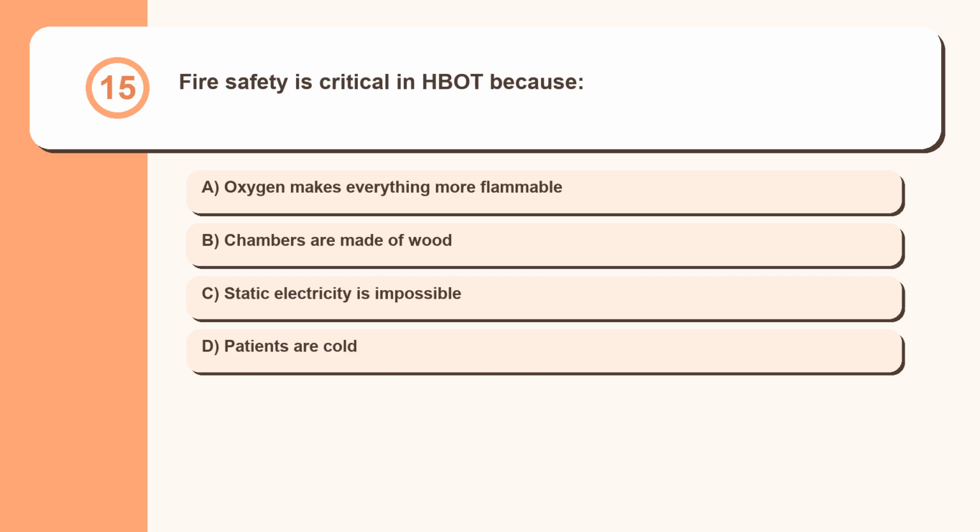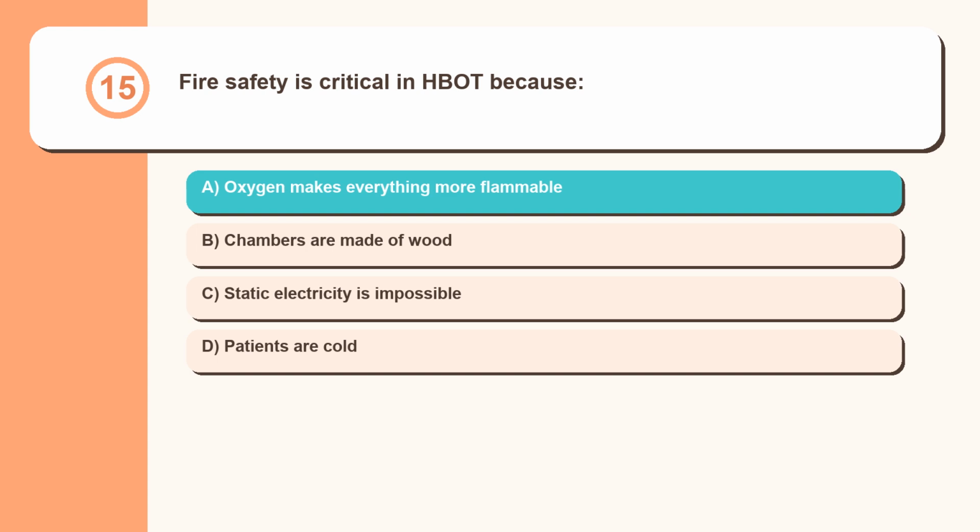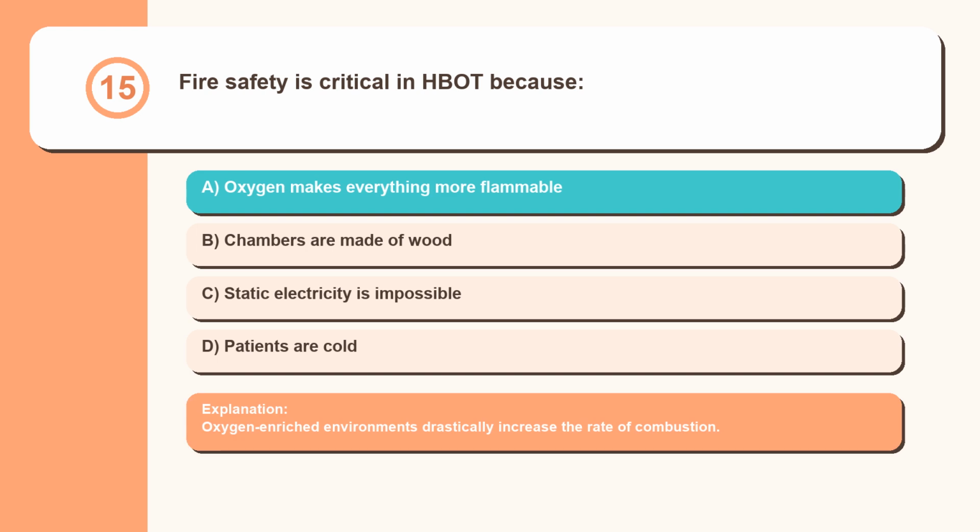Question 15. Fire safety is critical in HBOT because oxygen makes everything more flammable. Chambers are made of wood. Static electricity is impossible. Patients are cold. Oxygen-enriched environments drastically increase the rate of combustion.